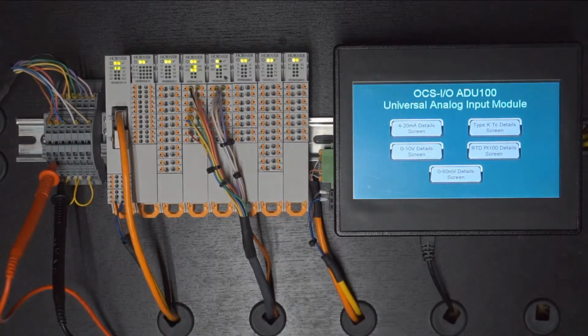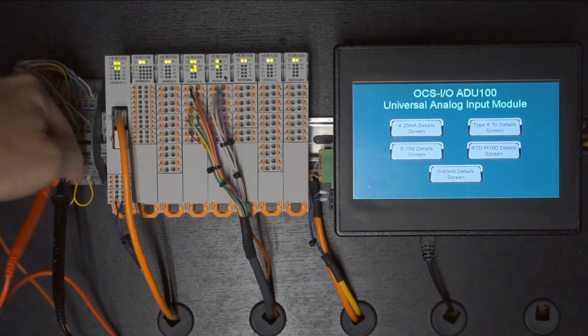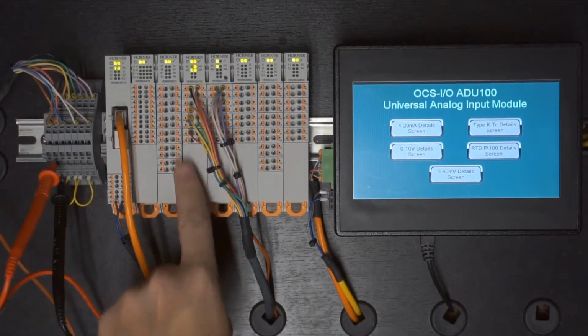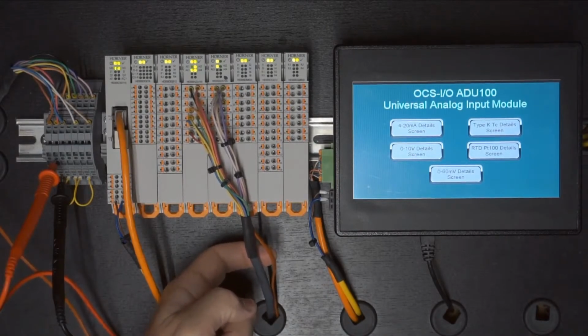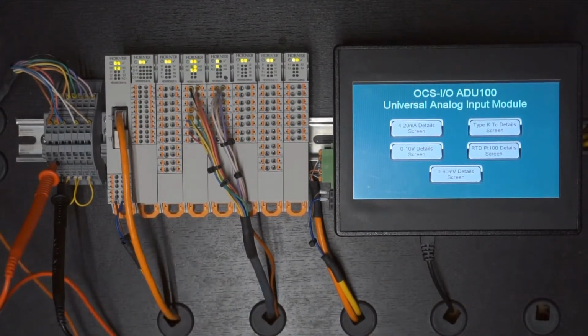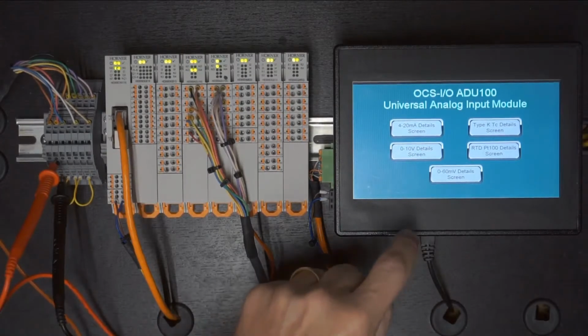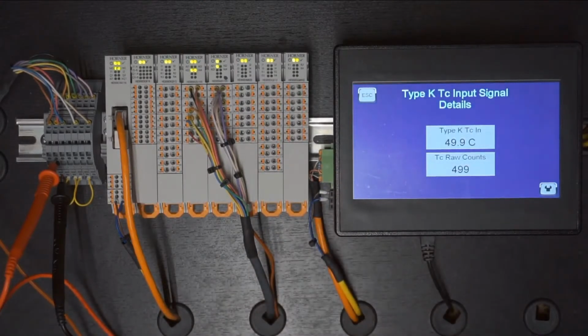All right, the next thing I want to show you is thermocouple. So I need to add my thermocouple probe to my simulator. Now, my thermocouple probe does not use these copper outputs here. It uses a special thermocouple extension wire type cable that connects to my thermocouple channel. Again, I need to switch my simulator offline from voltage to thermocouple. I've done that. Let's go to 50 degrees Celsius, and let's take a look at what it looks like on the screen. There we go.